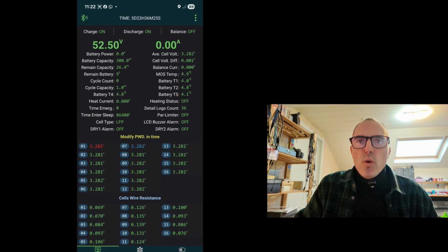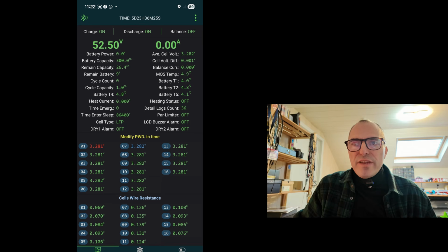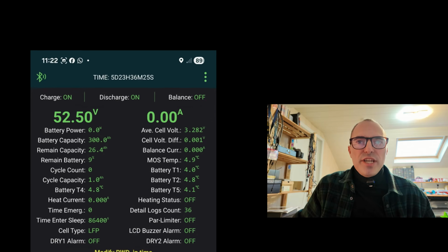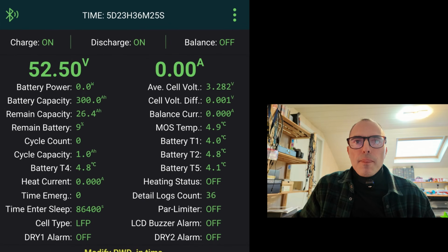The first screen is an overview, a real infotainment. It gives a global overview, but you can't change any settings here. On top we see the Bluetooth icon, means we're connected via Bluetooth. The time shows the time the BMS was active. Charge, discharge, balance gives the status of that option. You can switch this off, but then you have to go to the control menu. Standard charge and discharge are on. Balance becomes active when certain conditions are met. Later more on that.